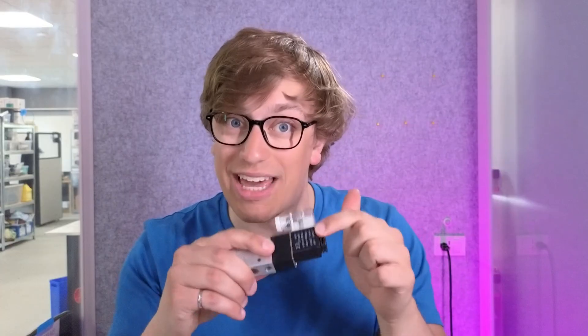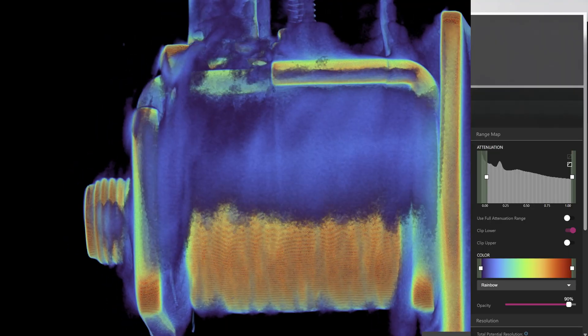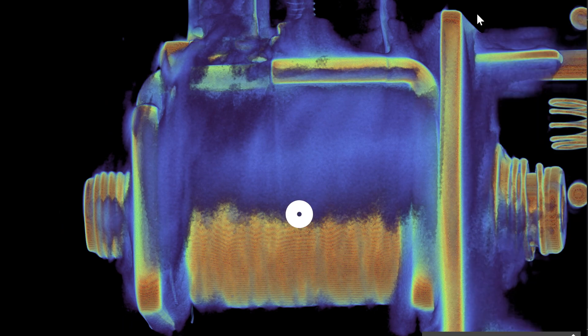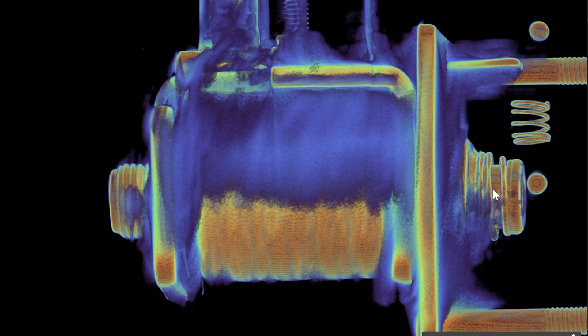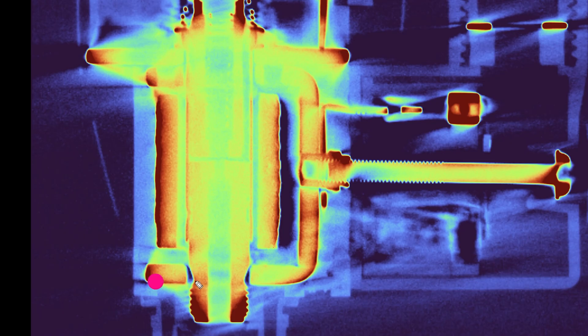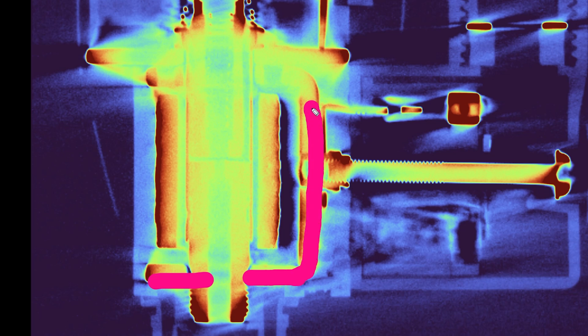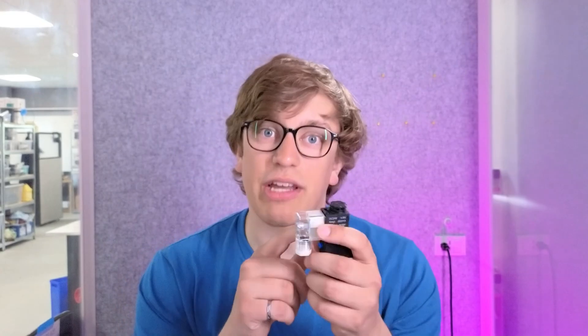This is the actual solenoid of the solenoid valve, and it is a couple hundred turns of copper wire wrapped around a tube. Right here we have our gland. In here we have our spade connections, which aren't exactly on the cross section so they don't show up. And that metal frame is actually what this screw here is going directly into—a pressed insert that goes into that steel jacket that this screw can secure to.